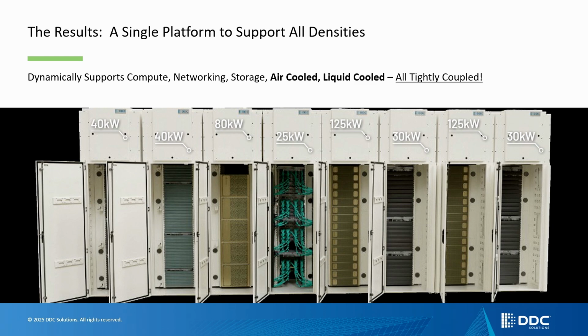We're improving efficiency significantly because we're only cooling a very small amount of air, and this combination of both liquid and air in one cabinet ensures that things like memory, storage platforms, et cetera, that aren't currently liquid cooled have the required cooling even up to 100 kilowatts worth, while the rest of the workload can be offloaded to the liquid to chip system.